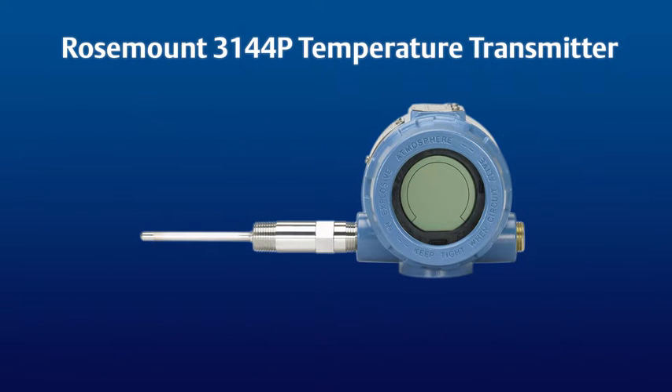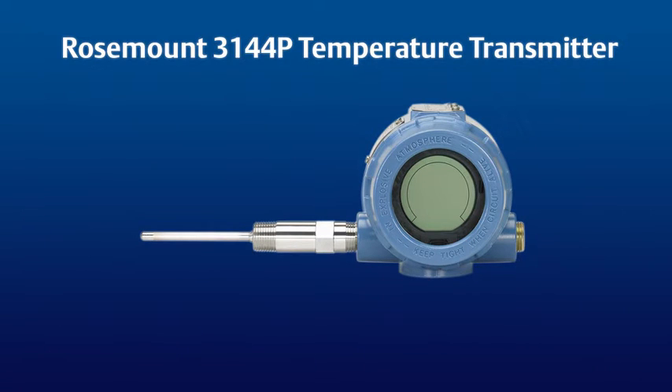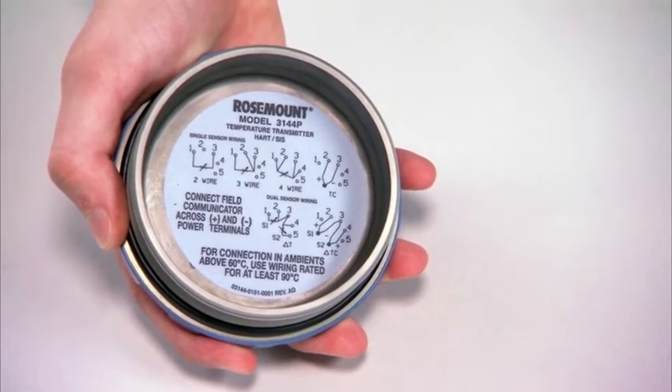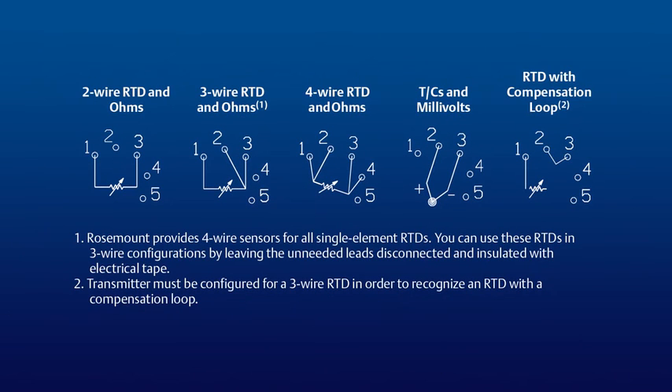The Rosemount 3144P Temperature Transmitter provides industry-leading accuracy, stability, and reliability. This video will demonstrate how to accurately wire and configure the most common temperature sensors that can be used with this transmitter. Note that inside the transmitter's back cover are wiring diagrams printed for reference. These wiring diagrams are also provided inside the Quick Start Guide.